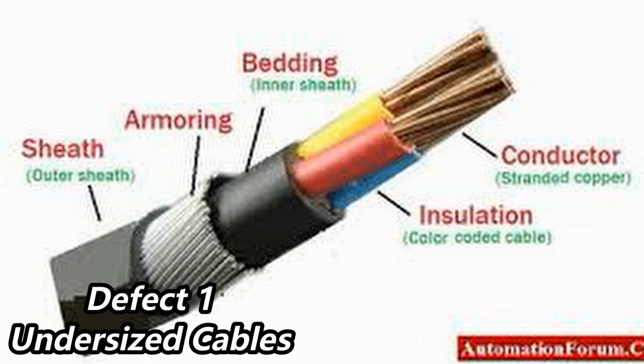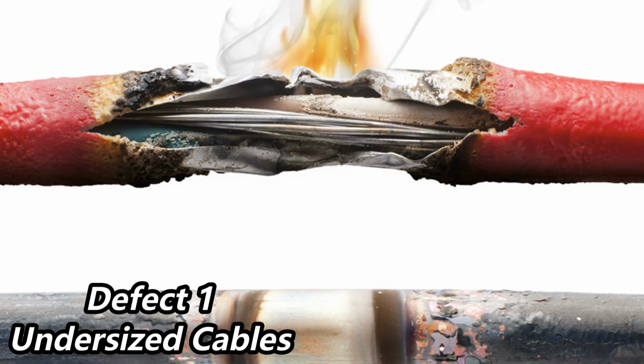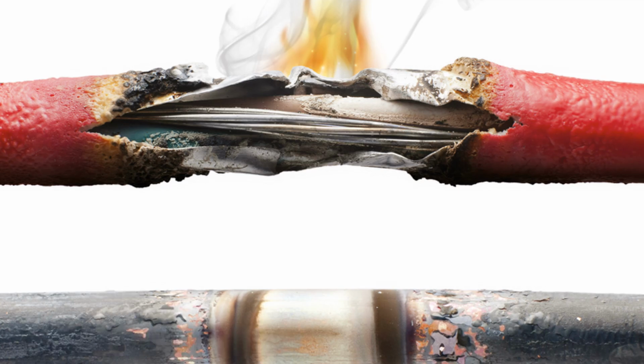One of the most common and dangerous issues is undersized cabling. Cables are selected based on current, the installation method, the ambient temperature around the cable, and grouping, not guesswork. Okay? In many new homes, cooker circuits are wired with lighting grade cable. Air conditioning units share undersized radial circuits. Socket rings are converted into overloaded spurs. Undersized cables don't trip breakers immediately. They overheat slowly, degrading the insulation around the cable until ignition occurs.